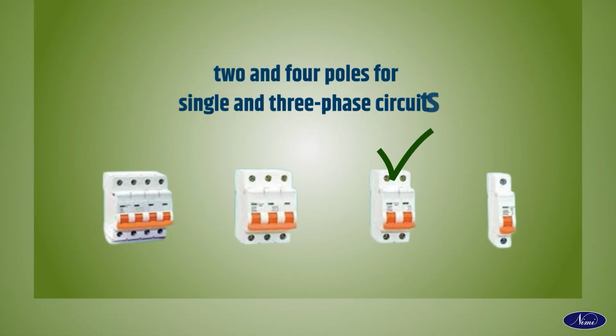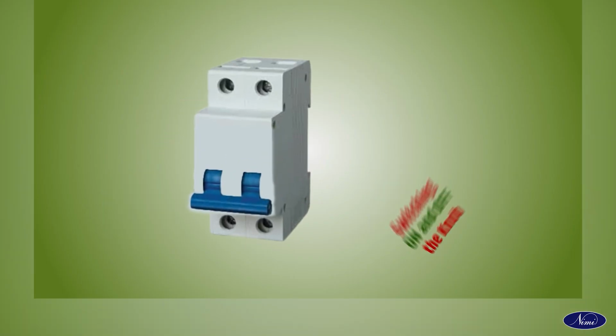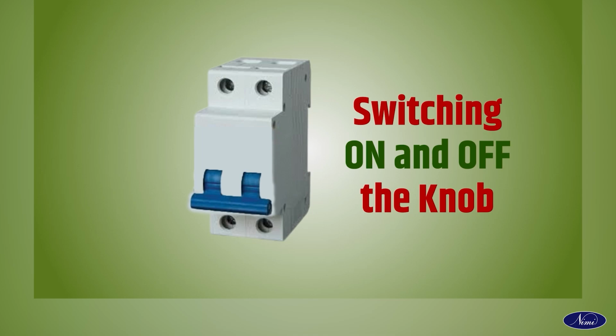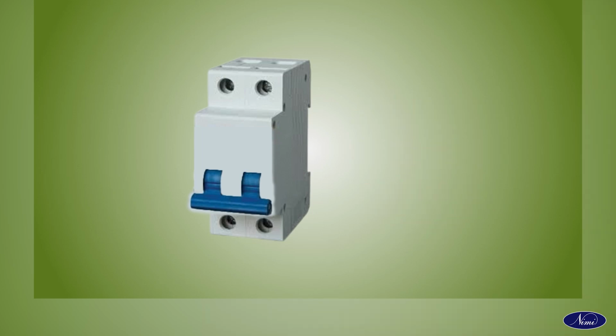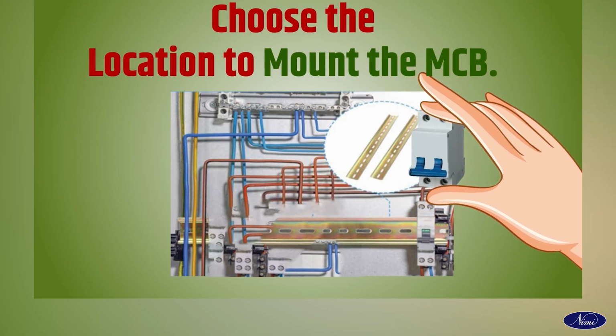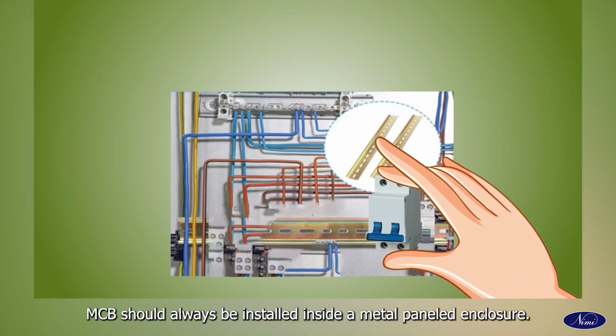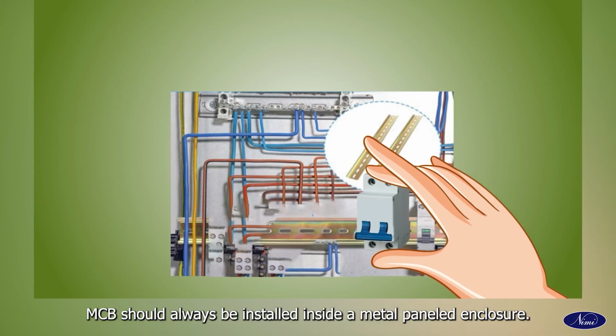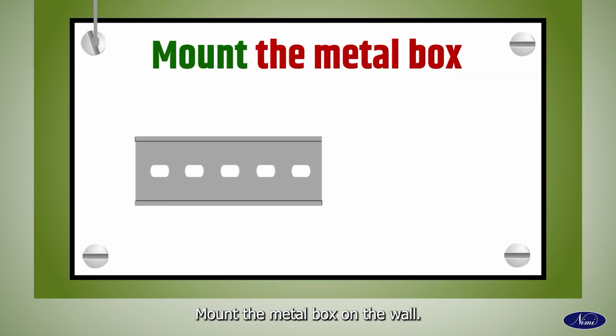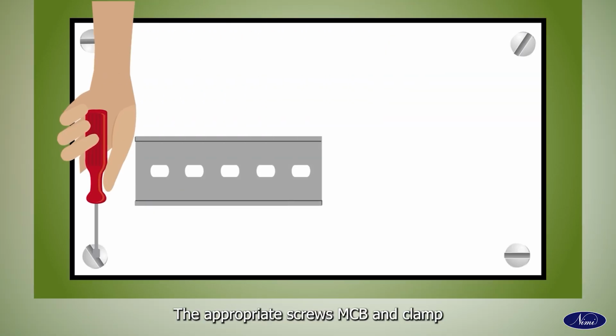Always prefer the 2 and 4 poles for single and 3-phase circuits respectively. Check the MCB manually by switching on and off the knob. Ensure the knob falls quickly when pulling it down. Choose the location to mount the MCB. MCB should always be installed inside a metal paneled enclosure. Mount the metal box on the wall with the appropriate screws.